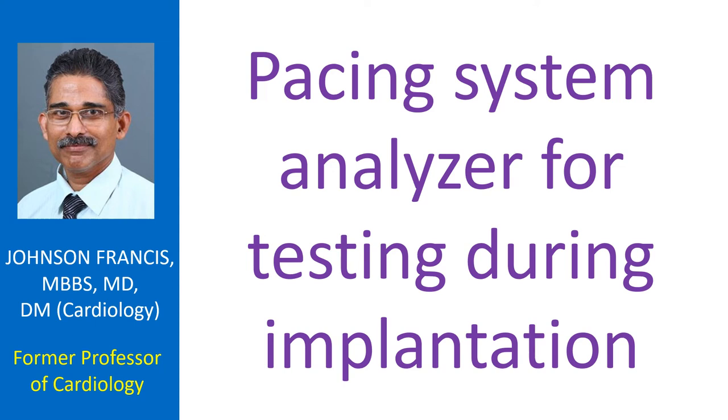Pacing system analyzer is used for testing various parameters like R wave amplitude, pacing threshold, and lead impedance during implantation of a permanent pacemaker. It can also deliver temporary pacing stimuli for supporting the heart rate if needed during the implant procedure.